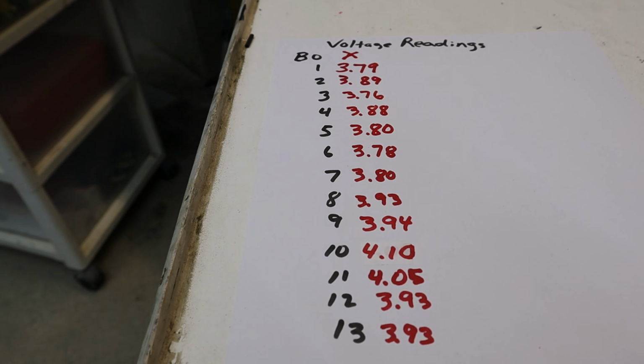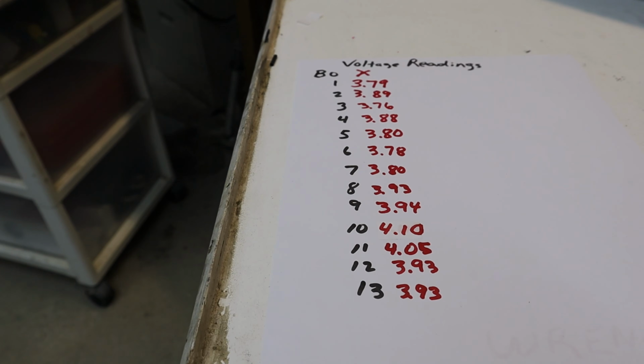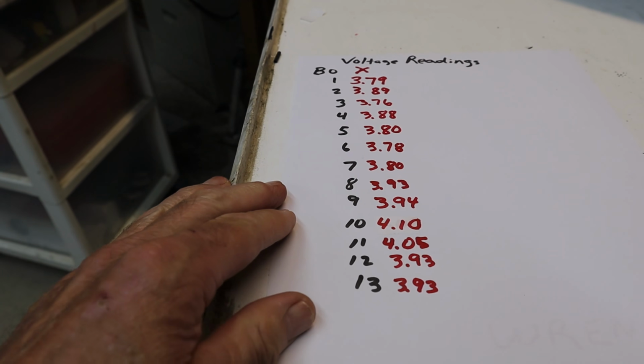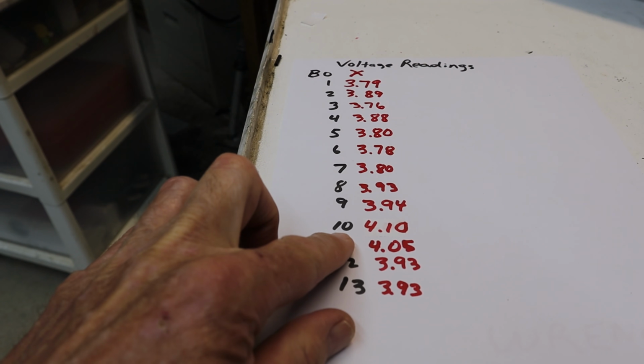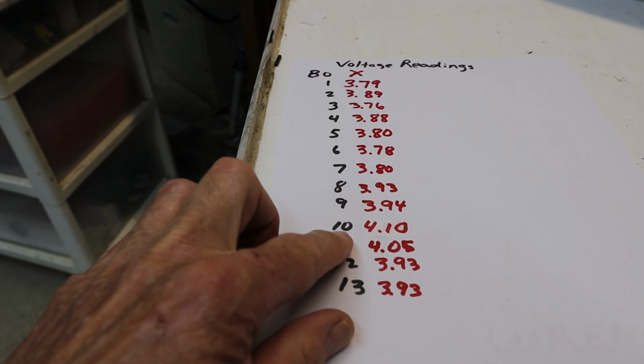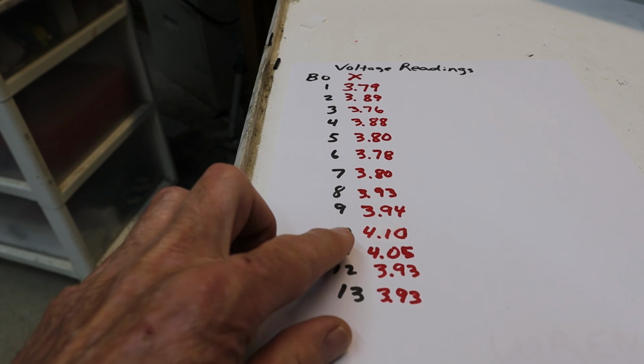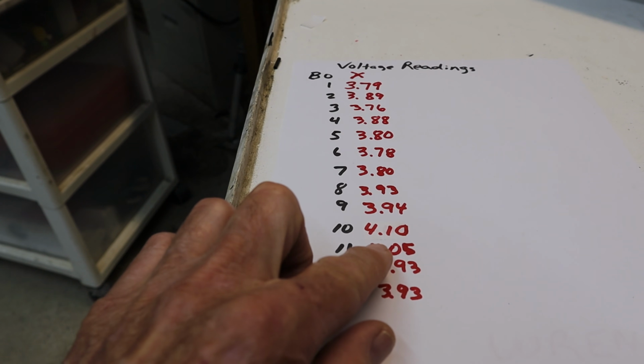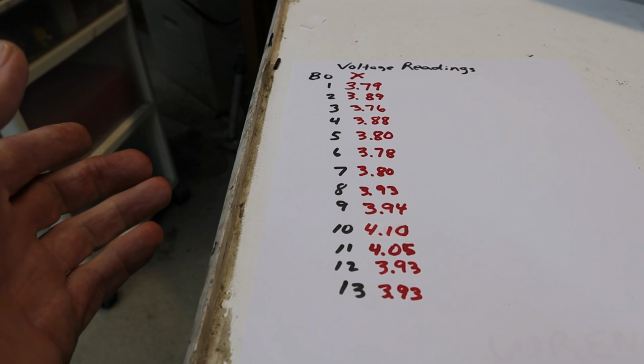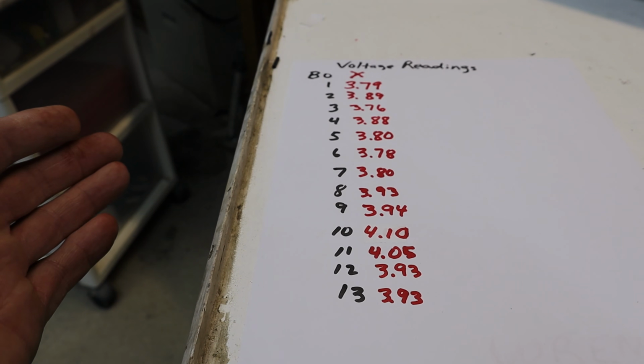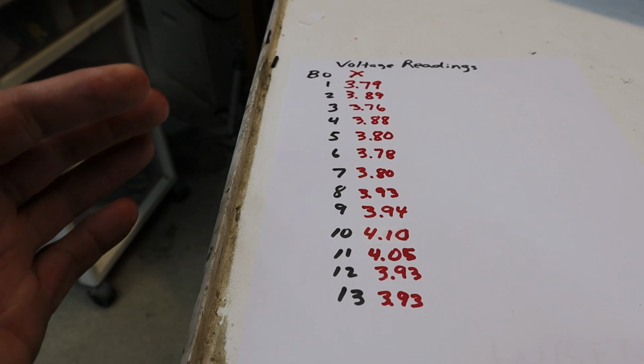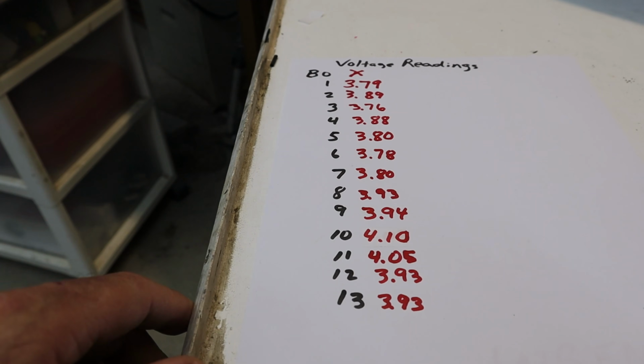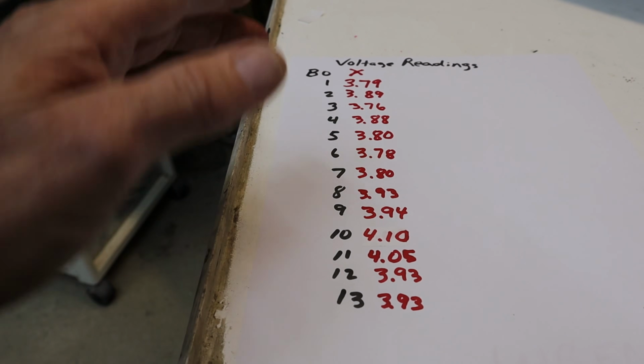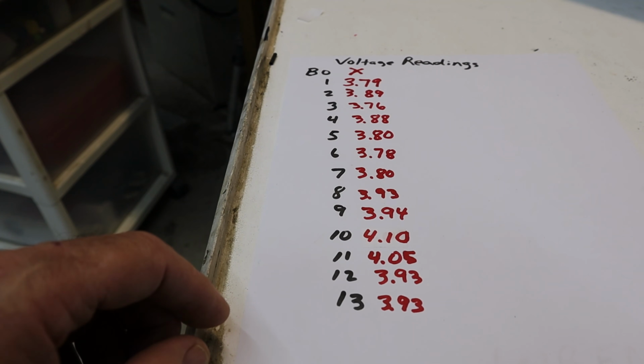So as you can see, this battery clearly is not in balance. One further point to note: had this battery been in balance, all the readings would probably have been within plus or minus 0.02 or 0.03 of a number - for example, if the highest number were 4.1, the lowest would be around 4.07, all within that range. But as you can see, this battery clearly is not in balance.